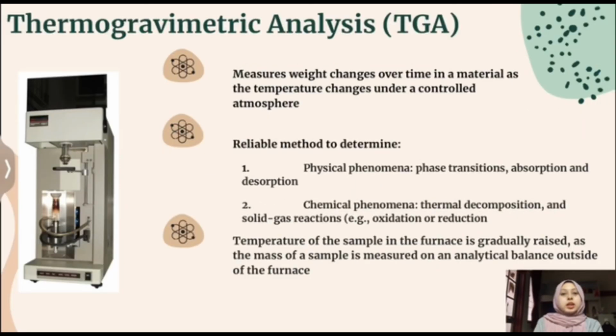Thermogravimetric analysis measures weight changes over time in the material as the temperature changes under a controlled atmosphere. This machine is able to study physical phenomena such as phase transitions, absorptions, and desorptions, while the chemical phenomena include thermal decomposition and solid-gas reactions, such as oxidation and reduction. The temperature of the sample in the furnace is gradually increased as the mass of the sample is measured on an analytical balance outside of the furnace.